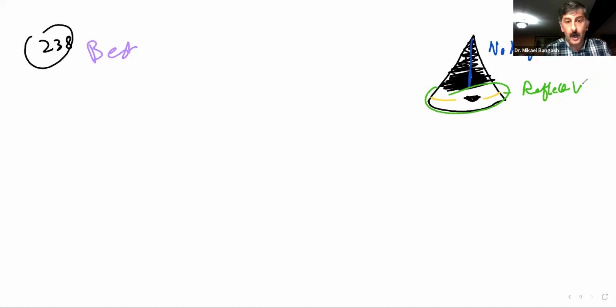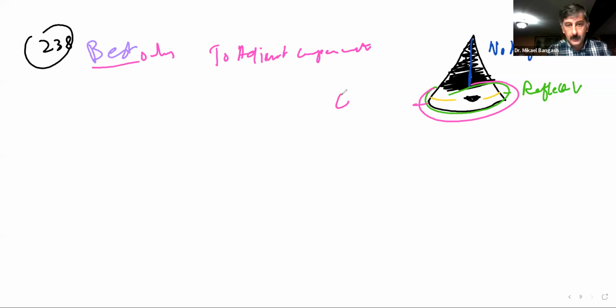Now, ladies, the best option here, actually in this instance the only option, is to adjust your compensation. Down here, at this great depth, we have compensation, but we may still need to increase the compensation in this area here, because it might have been too low a compensation. That may be why in this area we still don't have any reflections.